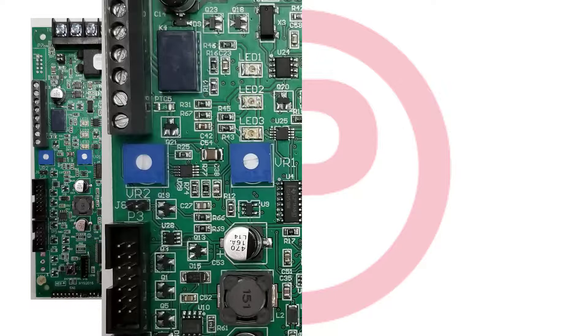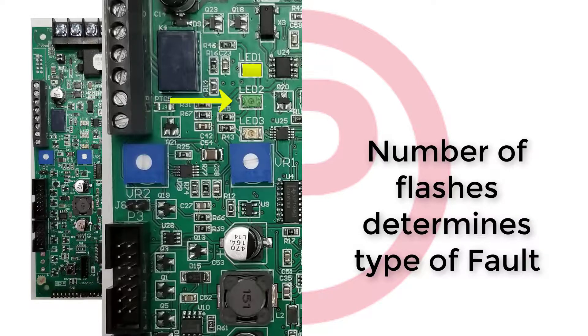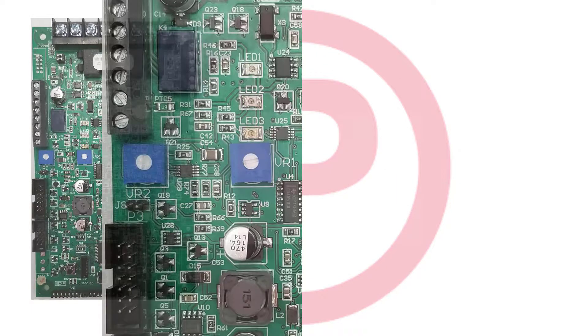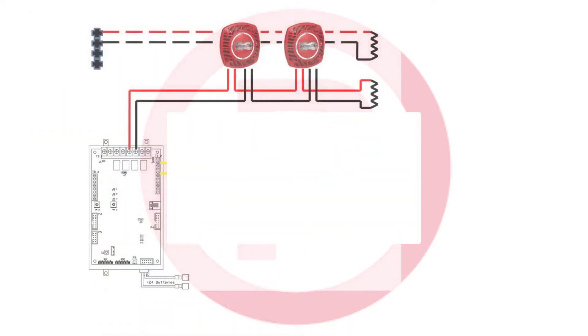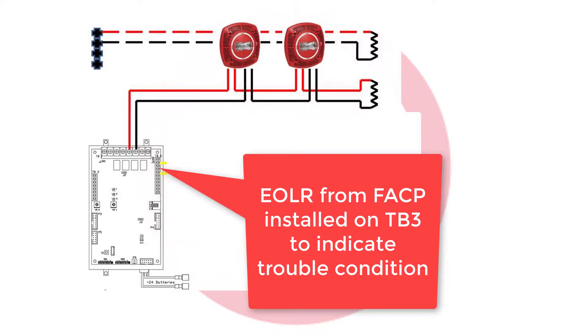If a fault or trouble exists on the system, the green LED will flash while the yellow LED number 1 remains illuminated. The number of flashes by the green LED is a code which will tell you the specific type of fault. During a fault condition, the contacts which the fire alarm control panel is monitoring will open, indicating the fault to the panel which will provide enunciation.